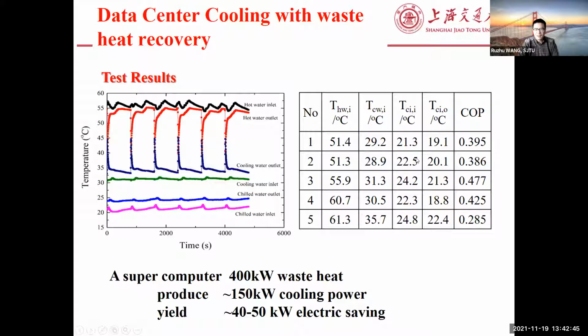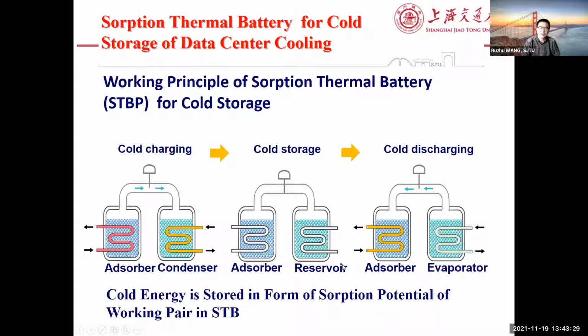So we made a test powered with about 50 degree to 60 degree hot water, and this just shows the COP values. And we get the cooling water about 20 to 24 degrees centigrade. So for a supercomputer, usually if it has 400 kilowatt waste heat, it could produce 150 kilowatt cooling power. So in this case, it could save about 40 to 50 kilowatt electricity. So this is used for the electrical powered chiller actually. So we made this kind of balance and find that this kind of design is reasonable. And now we are pushing the project in collaboration with Huawei for the data center.